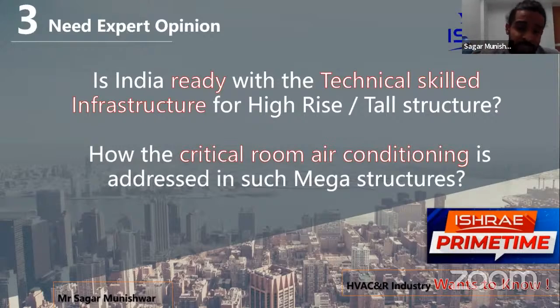Those service floors will be equipped with a plate heat exchanger, breaking the system from 0 to 70 meters, and from 70 to say 140 meters with another system pumping chill water to the upper floors. This requires sufficient space and height in the building, which means an integrated approach from the architect, the client, and the structural engineer.